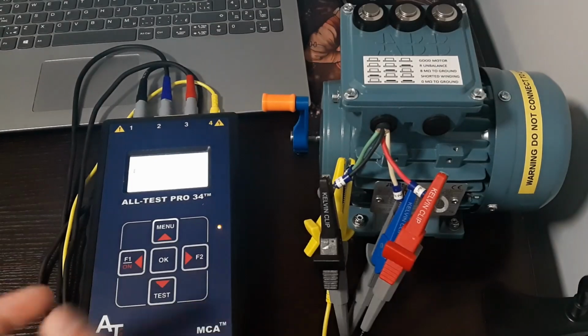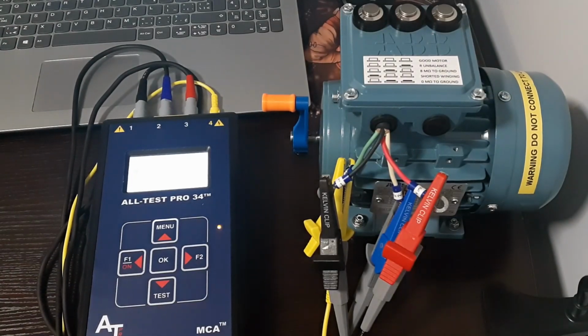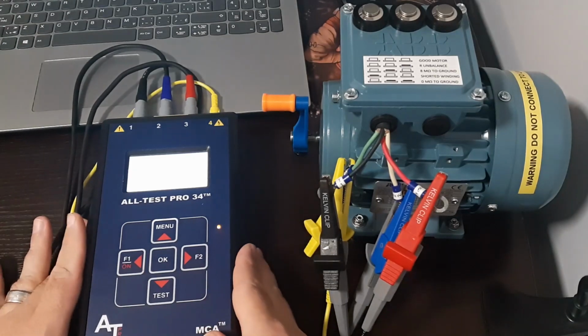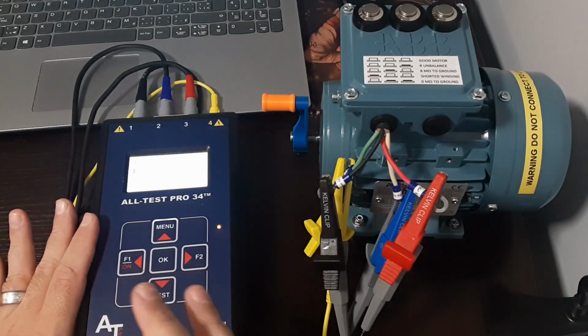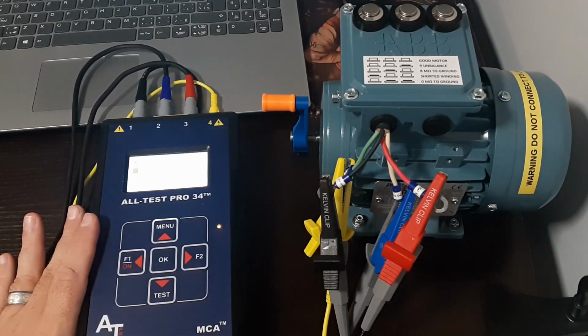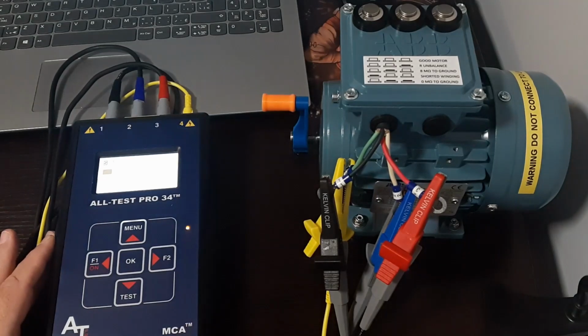So right now, we've already done the insulation test, which has passed, and the static test, which it is doing right now. That static test essentially also does the continuity as well. All the tests fail if the continuity is not there. So we're already testing for more than what a multimeter and a megohmmeter do. And I believe this is the last phase here.